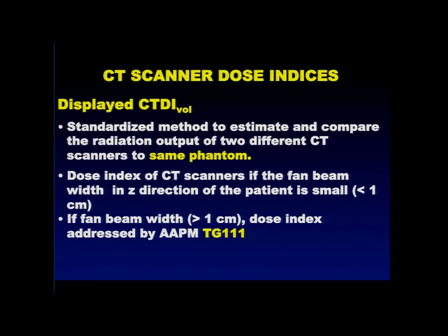And that's why TG111 was started. There's TG200, which is developing a standardized phantom to make these measurements. And the idea is that we won't make those measurements in the field because nobody wants to carry a 70 centimeter phantom, because it weighs about 200 pounds. So the idea is we'll ask the manufacturers to make careful measurements in the factory, and they will give us correction factors for their model scanner to apply to our measurements in the field.